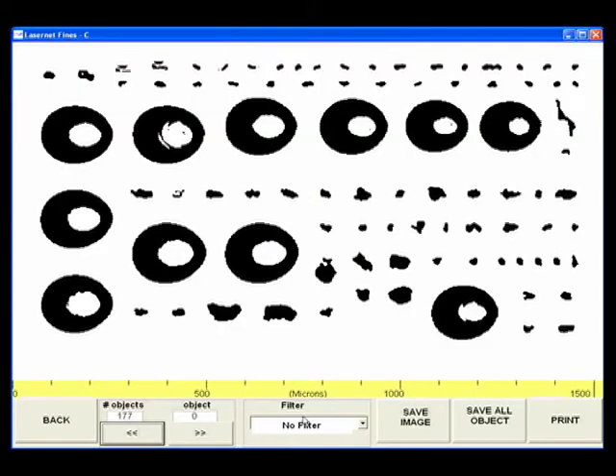The LNF also recognizes water droplets and automatically eliminates them from the results, giving a higher degree of accuracy than other particle counters.